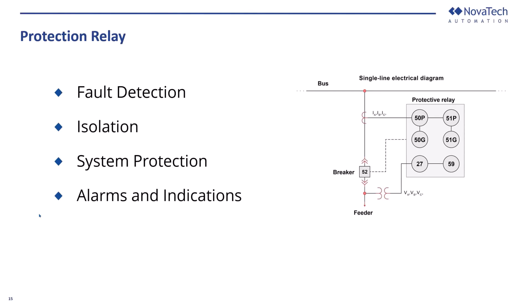Most of the IEDs have inbuilt alarms and indication capabilities too, whether visual or audible, so that system operators can be notified of any abnormal conditions. On the right-hand side, this is just a typical single line diagram. We've got a bus with a breaker and perhaps multiple feeders. It shows just one here, but realistically there will be multiple feeders. Then we have the CT and PT connected to a relay, where the relay can sense, based on the configuration and settings, different protective elements such as instantaneous overcurrent, time overcurrent, ground faults, and anything with under or over voltage. Depending on what circuit we are trying to protect, there would be different protective elements to protect that equipment.